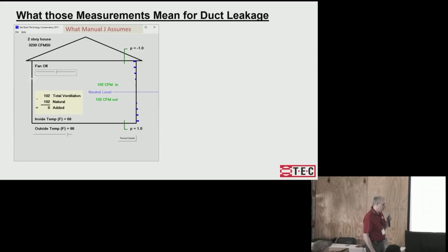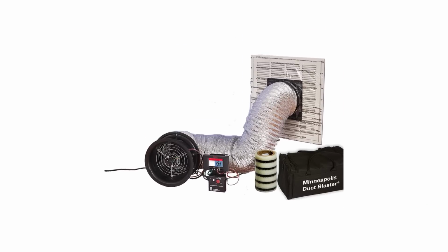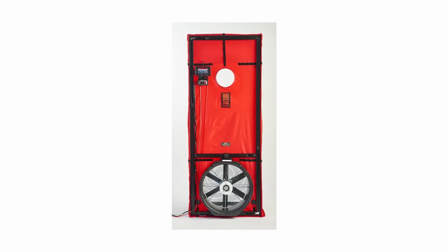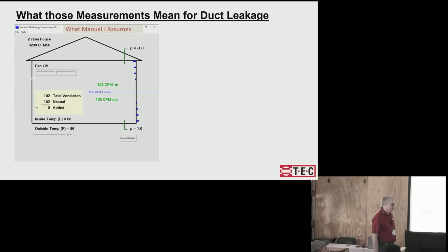Go ahead, Bill. We're going to do this. Another option to quantify the duct leakage is to use a duct blaster and measure, right? But in this case, the technician had a blower door available, easy, and he did it because he wanted it for his Manual J too. So you're going to see a way to say, if I have a blower door and I did that depressurization test, I can use this free tool and still back calculate the duct leakage from the blower door. This isn't the only way to do it, but it's sort of a backdoor way to say I don't necessarily need a duct blaster and a blower door. Yeah, and actually in this case, I would say maybe this is the front door approach, because a duct blaster test won't tell you how much it's leaking in normal operation, yeah.